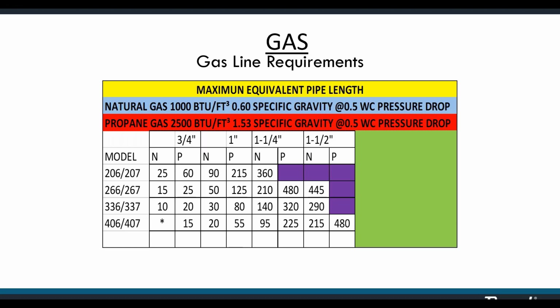You may find that the size of the heater will be dictated by the gas pipe. It's just barely possible that the client will not want to dig up their entire backyard to accommodate a new heater. All right. Now you can try a smaller sized heater, or depending on circumstances like codes in your area, you might be able to increase the pressure in the pipe and then regulate back down using a second regulator at the heater end to convert that pressure to volume at a pressure that's appropriate for the gas valve that is on the heater.